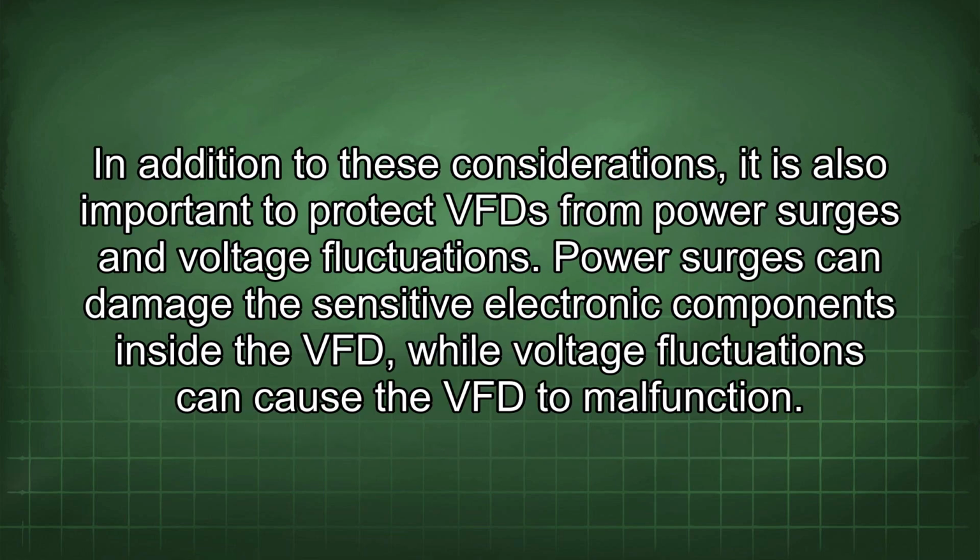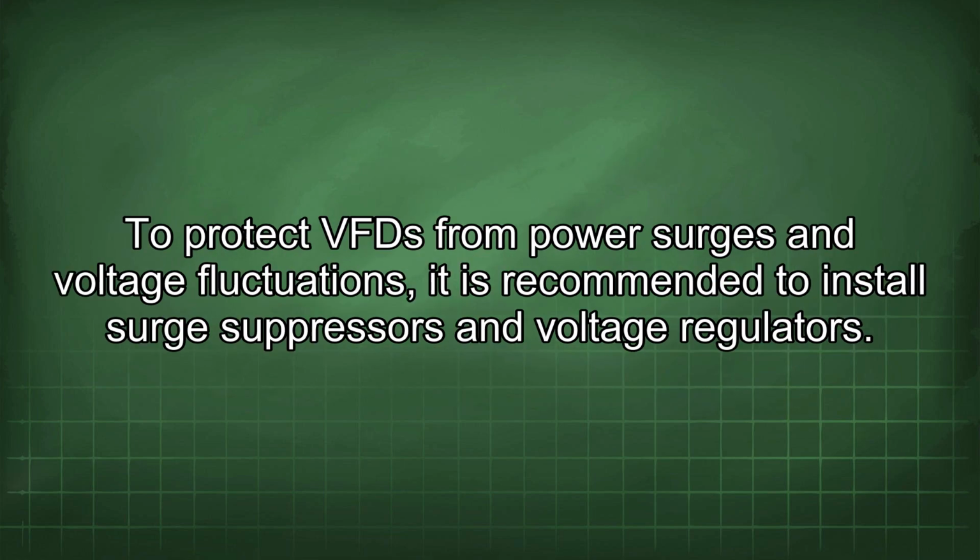In addition to these considerations, it is also important to protect VFDs from power surges and voltage fluctuations. Power surges can damage the sensitive electronic components inside the VFD, while voltage fluctuations can cause the VFD to malfunction. To protect VFDs from power surges and voltage fluctuations, it is recommended to install surge suppressors and voltage regulators.